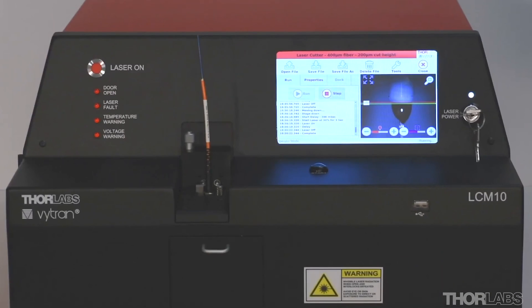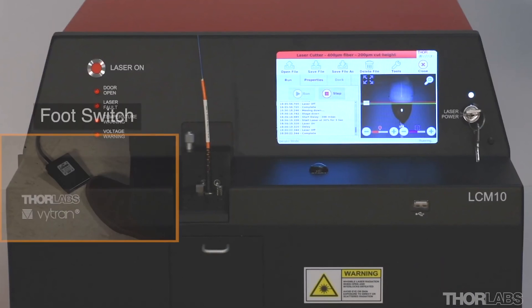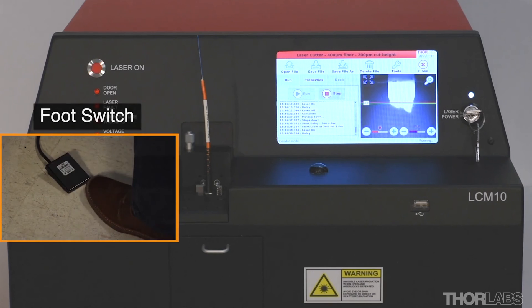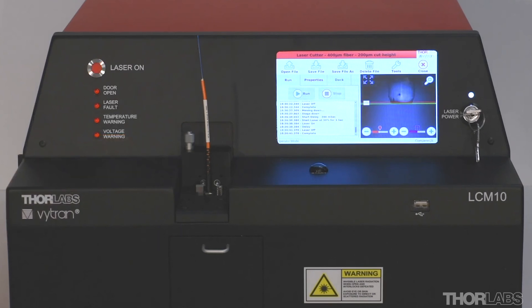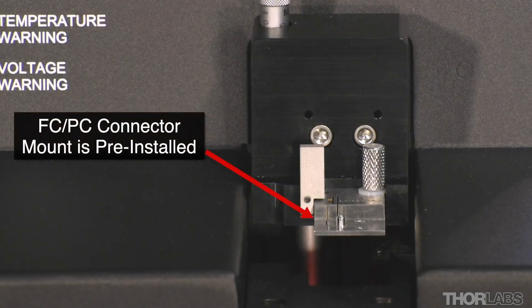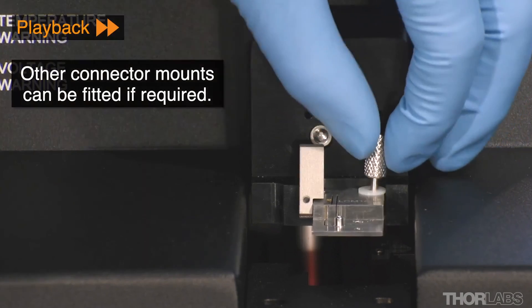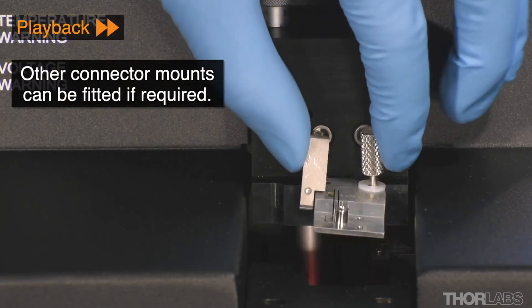If the operator's hands are occupied with handling fibers, a footswitch may also be used to initiate the cut, rather than pressing the start button on the front of the unit. The LCM10 comes with the FC/PC connector mount pre-installed. Other connector mounts and cannula stops can be easily fitted by the user if required.